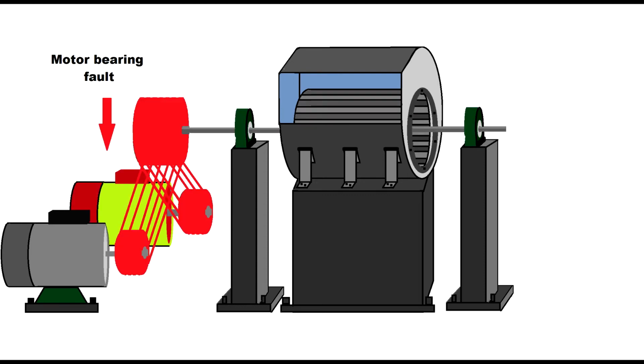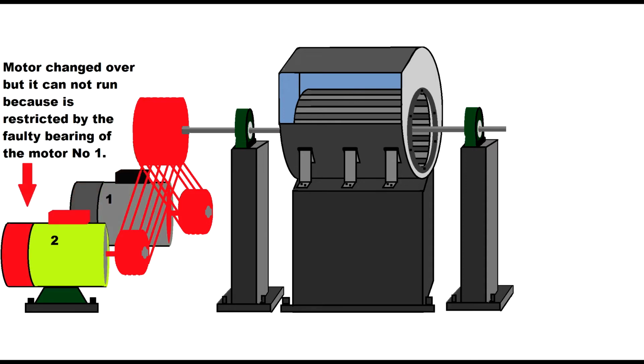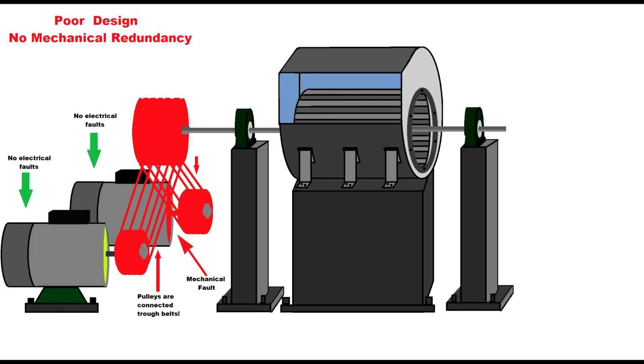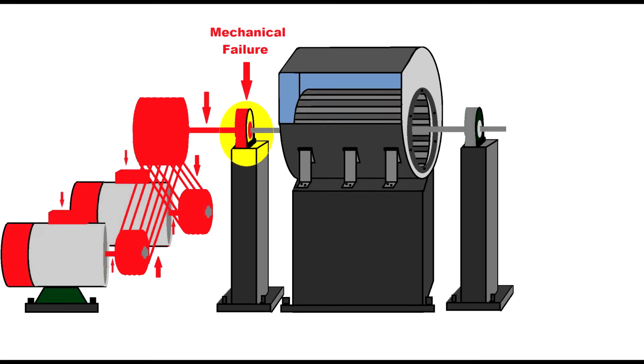If you have a mechanical failure like a bearing, you see these motors are connected to the belts, and regardless of which motor gets broken, the other motor will be affected and the system will stop because we don't have a mechanical redundancy. And if you look at the red arrow, you will see the parts that are affected. Can you imagine if you have a mechanical failure to the first plummer block? The bearings are gone. Through the shaft, through the pulley, through the belts, both motors are affected, and the fan will stop. You won't have a mechanical redundancy. So this is the bigger inconvenience when you use this type of system.